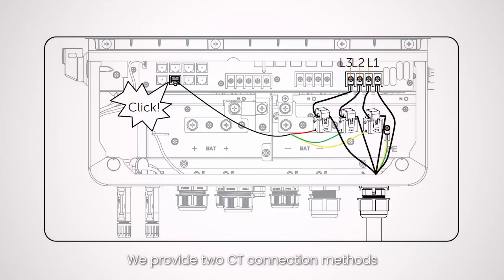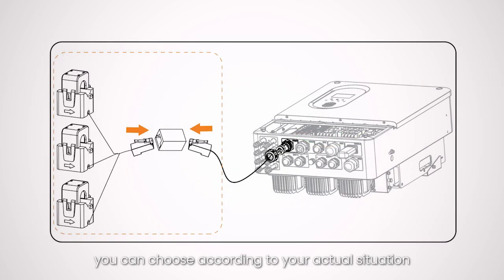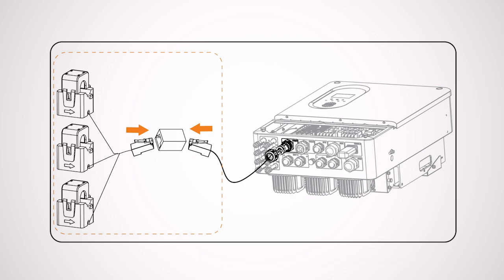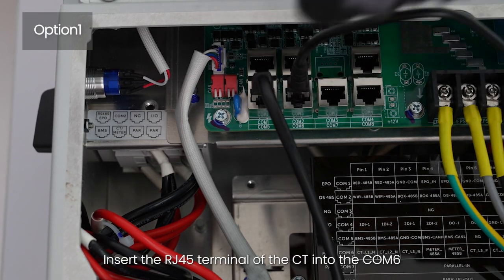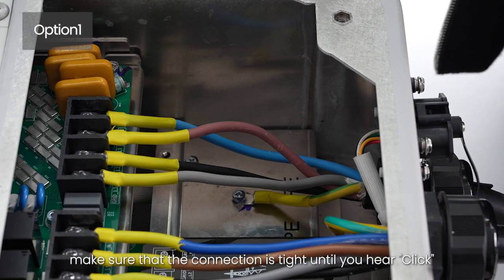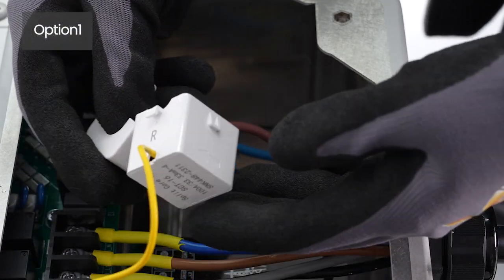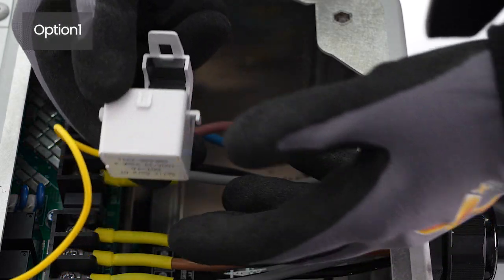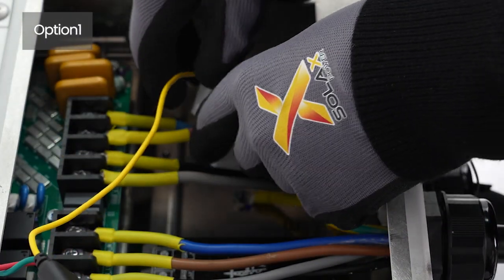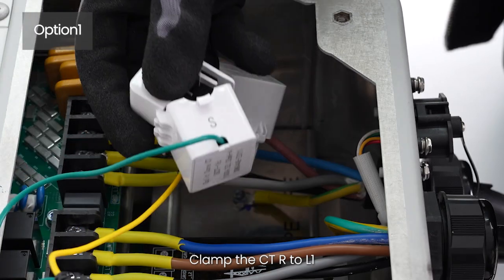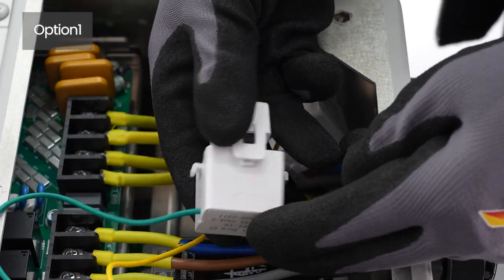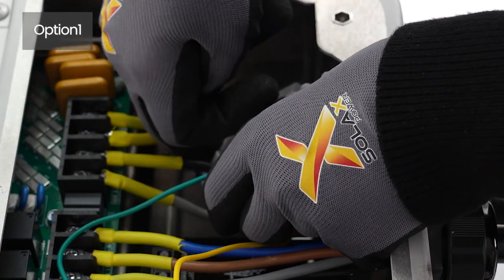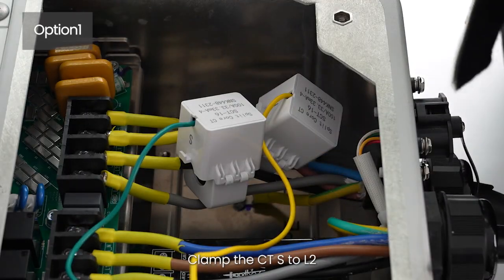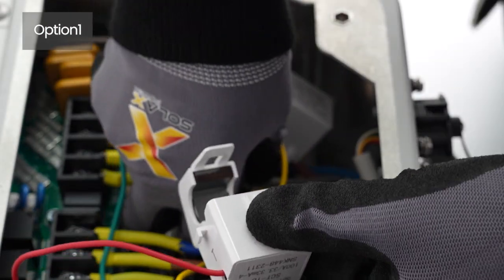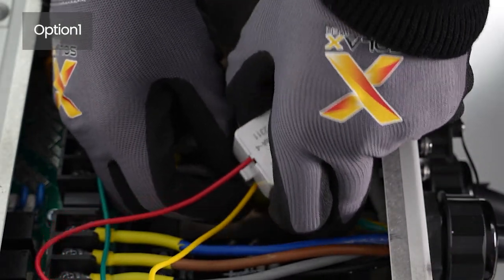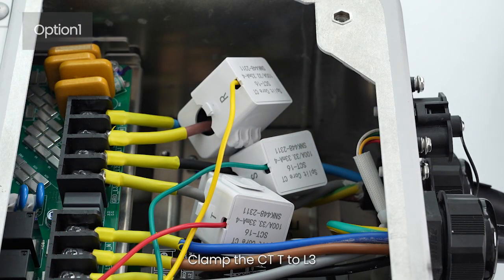We provide two CT connection methods. You can choose according to your actual situation. Insert the RJ45 terminal of the CT into the COM6. Make sure that the connection is tight until you hear click. Clamp the CT R to L1. Clamp the CTS to L2. Clamp the CTT to L3.